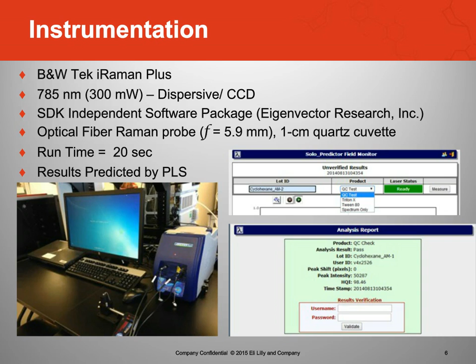Some of the challenges we were faced with is we wanted, again, as I try to keep this as simple as possible for the user. So we first approached this by looking at disposable polyethylene cuvettes, and that worked for a while. Unfortunately, we got enough of a difference in the backgrounds of the polyethylenes that we started running into modeling problems with background differences. I'll talk a little bit about the pre-processing of the spectra, but for all practical purposes, I didn't use second derivative, which probably eliminated this. But we stuck with a pretty simple pre-processing step.